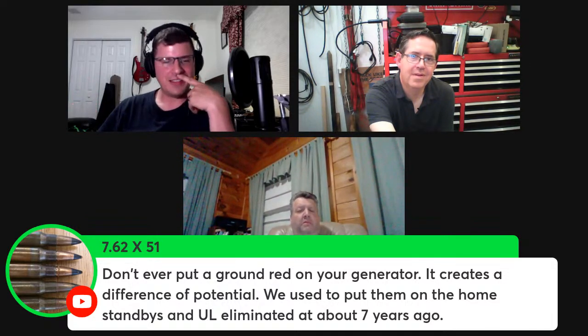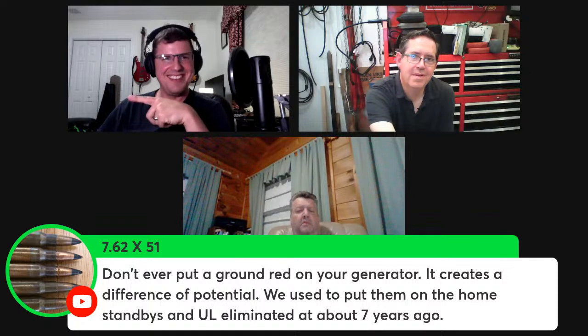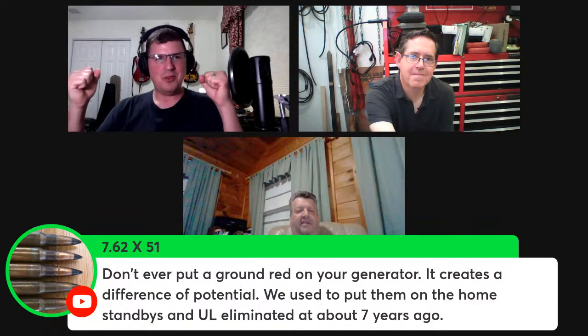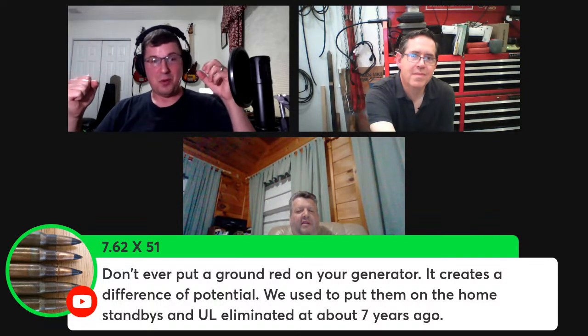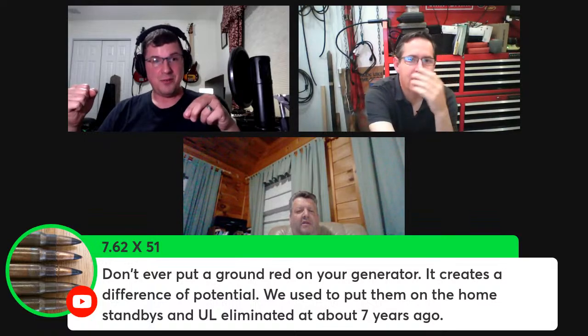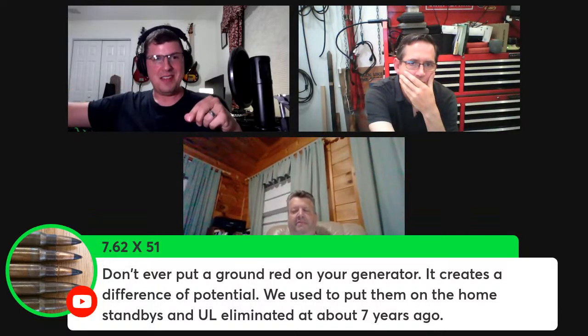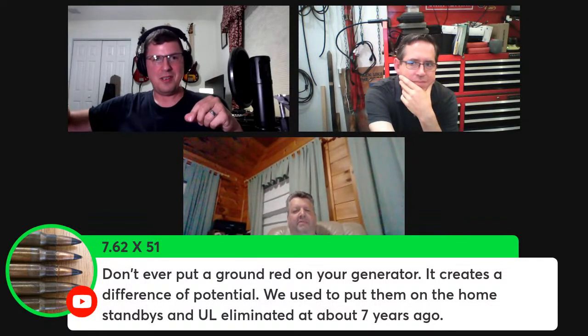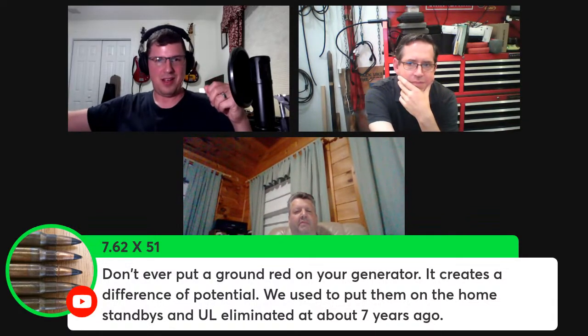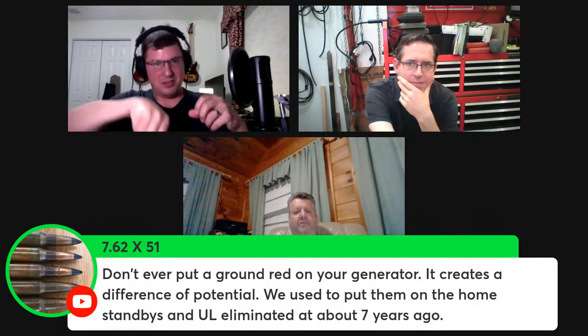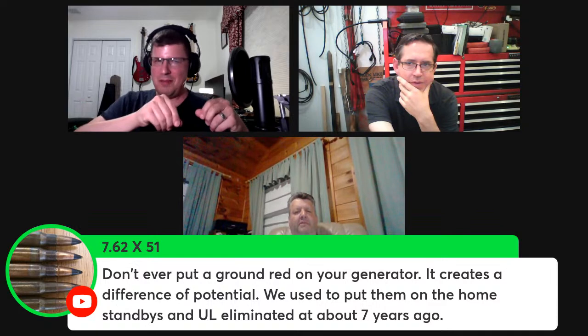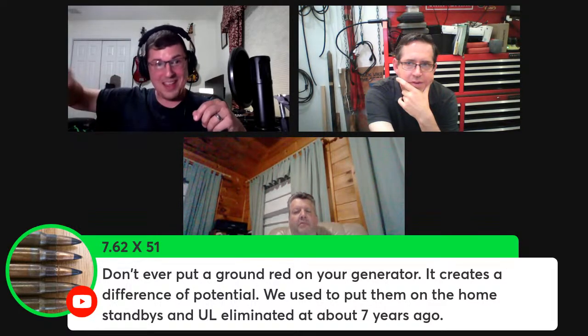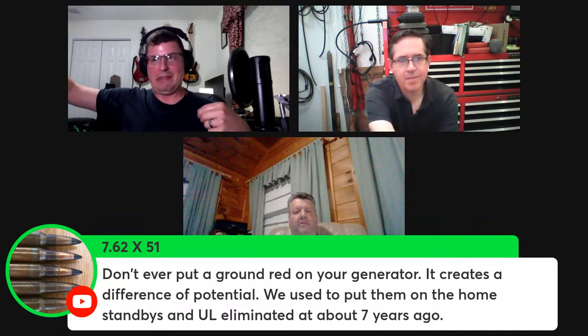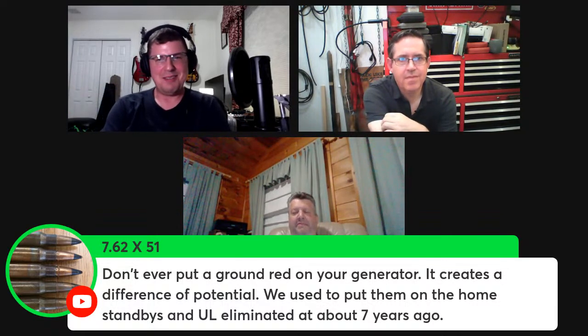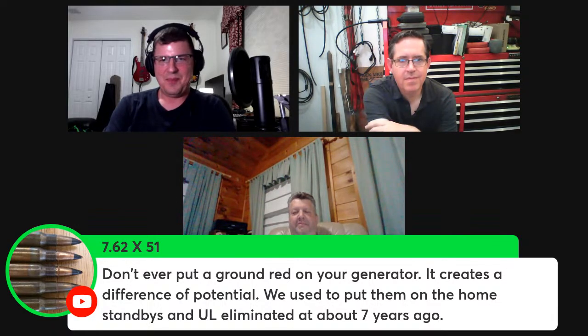There's another guy on YouTube we should probably get. He's done exactly this. He measured the potential, hammered two ground rods into the ground, and created a live wire to ground fault. He measured the potential difference from that live wire to the other ground rod. When he was right next to the ground rod and stuck his meter probe into the ground, there wasn't much voltage difference. The further away he got, the more the voltage went up. Interesting.